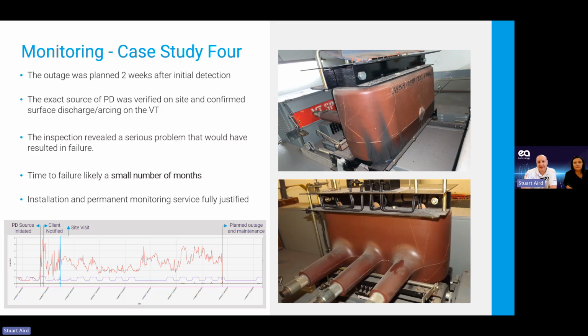They took it out, and you can see in the top corner here some significant burning and tracking on there. So I don't think this would have lasted very long. So if we go back to thinking about how we could, if we were doing a handheld survey, if we were doing one every year, you've probably got 1 in 4, 1 in 5 chance of catching that on your handheld survey. If you went in the week before this, you won't pick anything up, and you won't be coming back then for another year. So then you think, well, maybe we need to do our handheld surveys a bit more often.